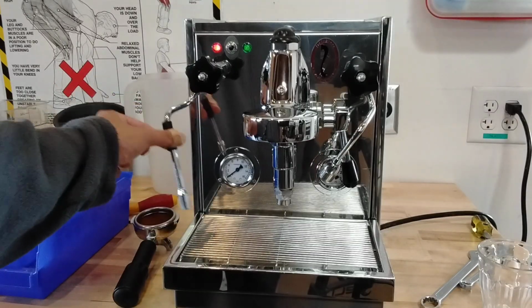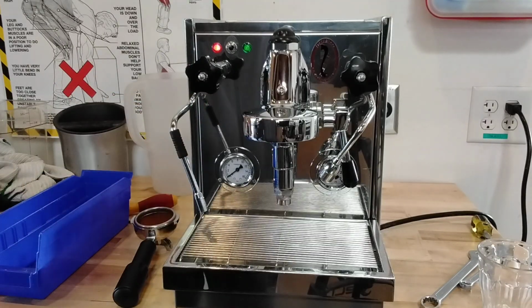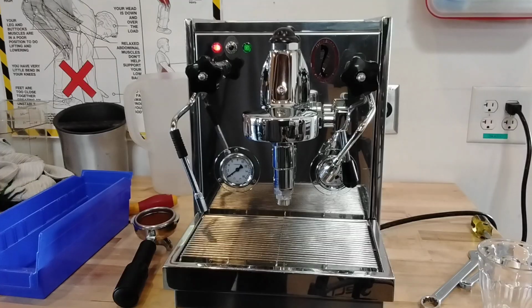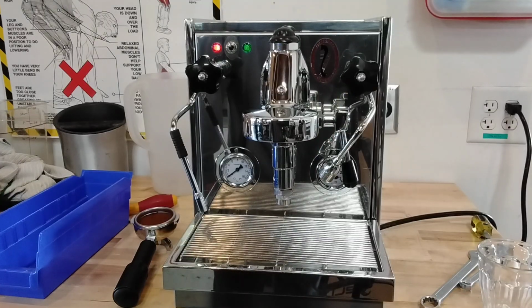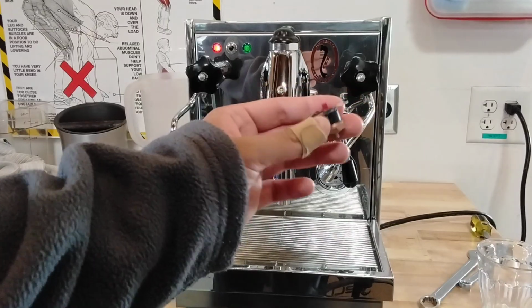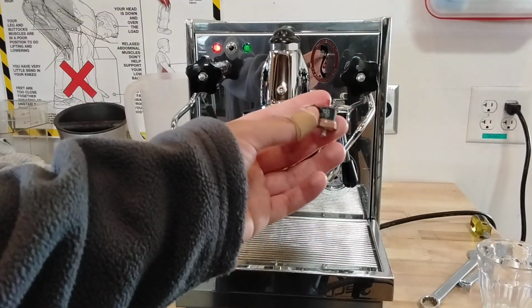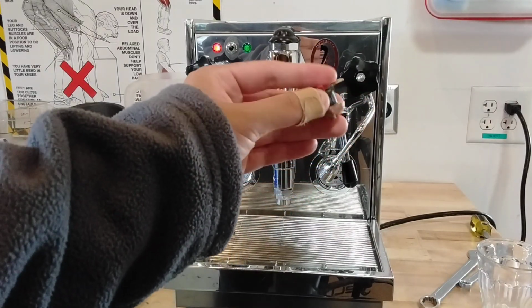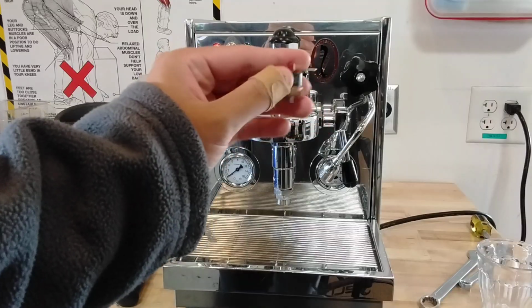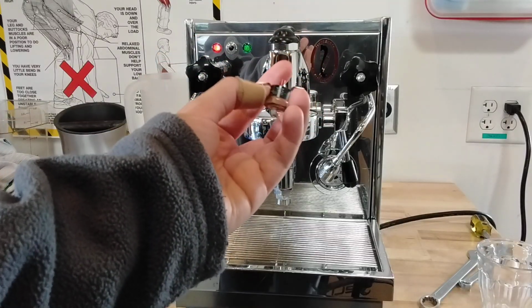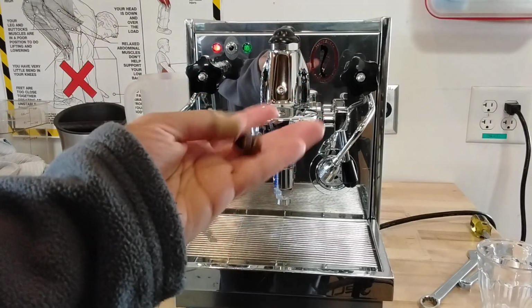It came in because the machine was not heating, the boiler. This is a heat exchanger, so the only boiler in there is a steam boiler, and it was just not heating up. What I found is actually the safety switch right here. The connection between the two connections here was not working. Even the button doesn't want to press in, so it's not tripped.